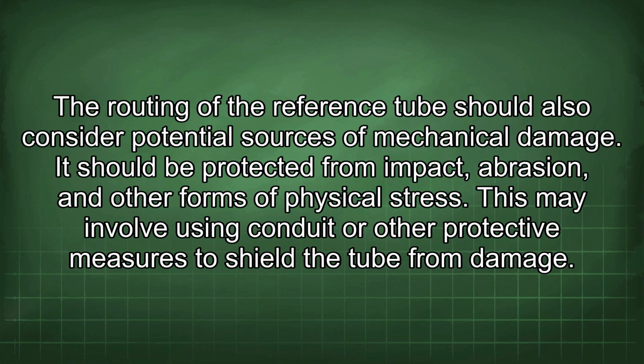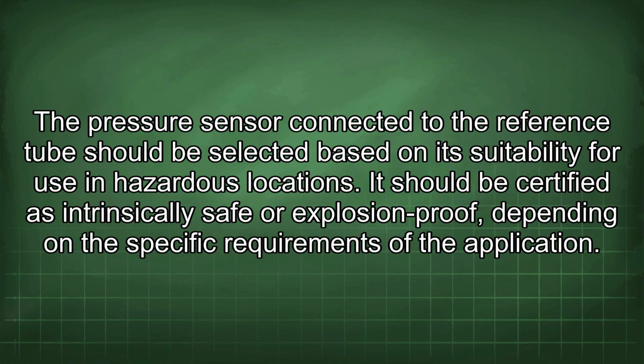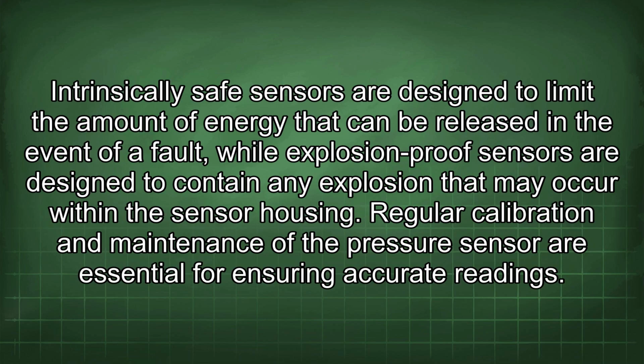The routing of the reference tube should also consider potential sources of mechanical damage. It should be protected from impact, abrasion, and other forms of physical stress. This may involve using conduit or other protective measures to shield the tube from damage. The pressure sensor connected to the reference tube should be selected based on its suitability for use in hazardous locations. It should be certified as intrinsically safe or explosion-proof, depending on the specific requirements of the application. Intrinsically safe sensors are designed to limit the amount of energy that can be released in the event of a fault, while explosion-proof sensors are designed to contain any explosion that may occur within the sensor housing.